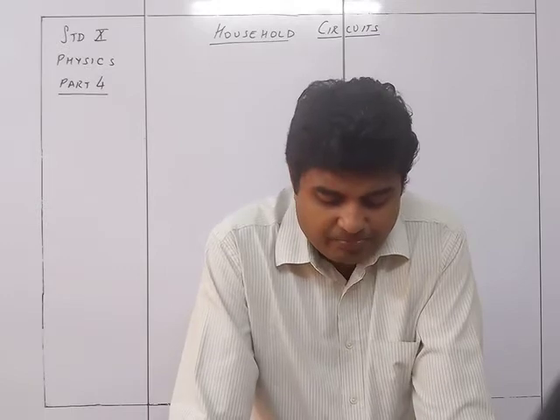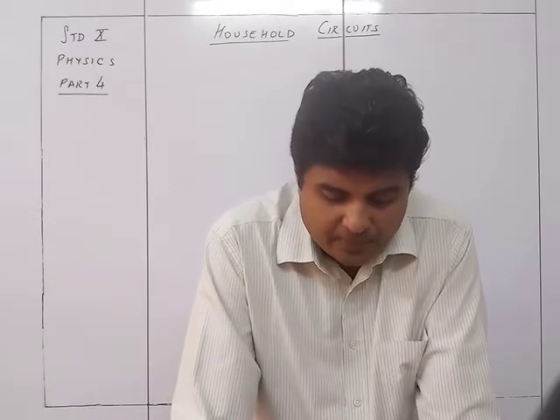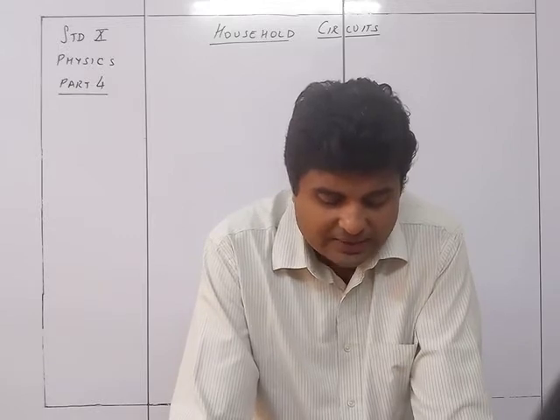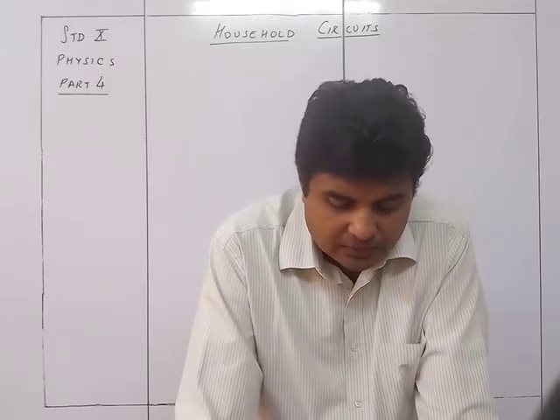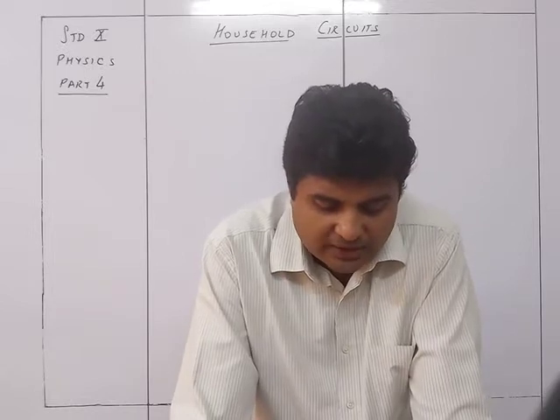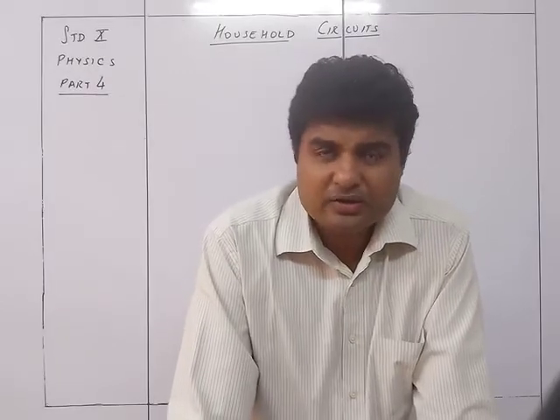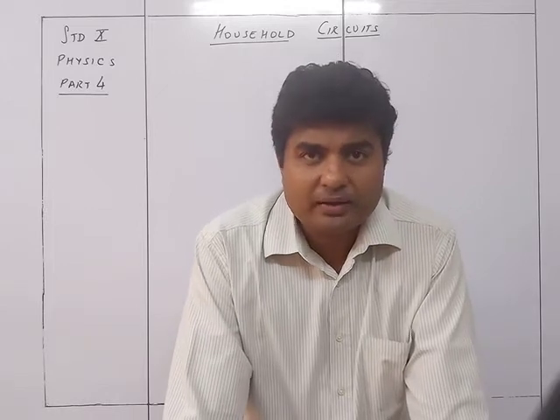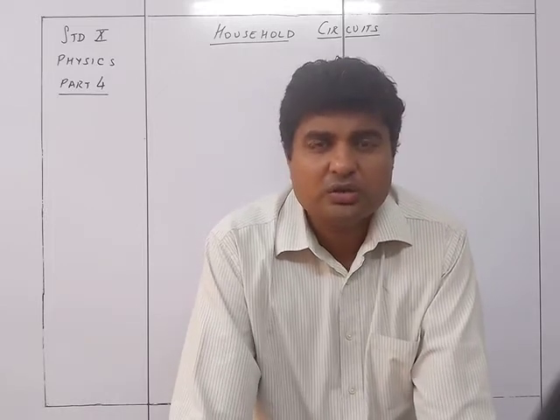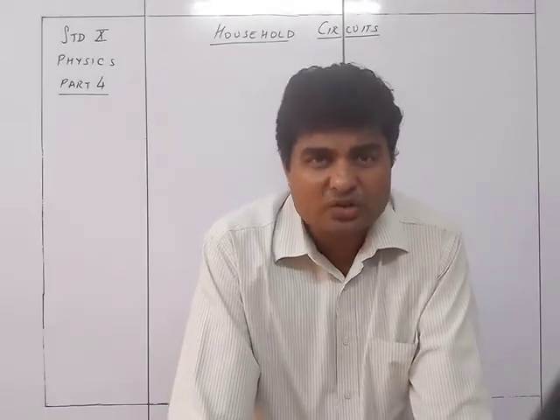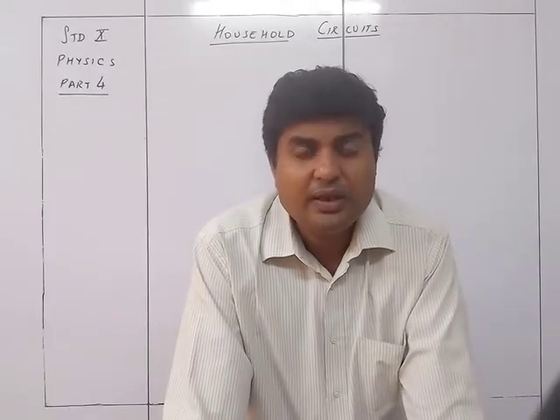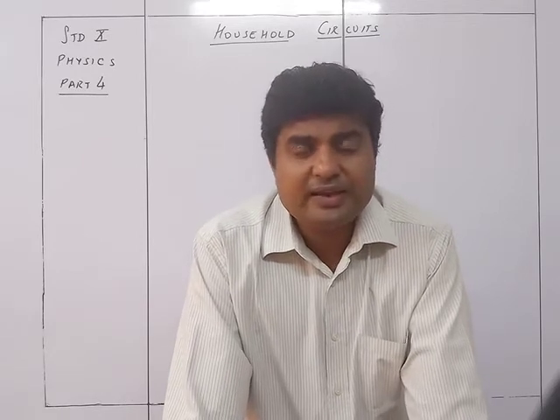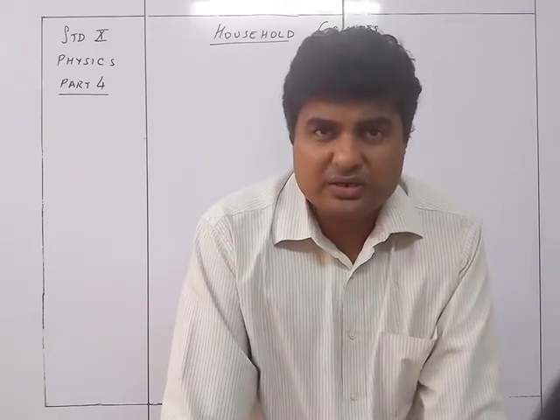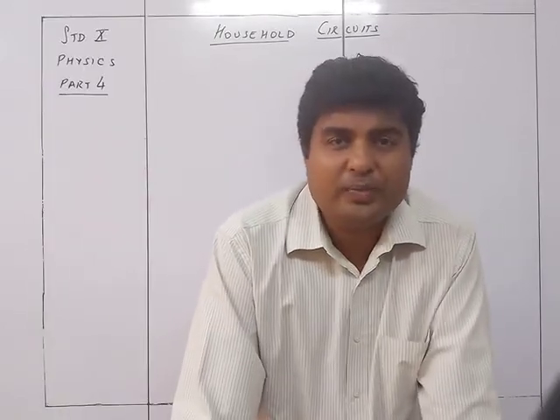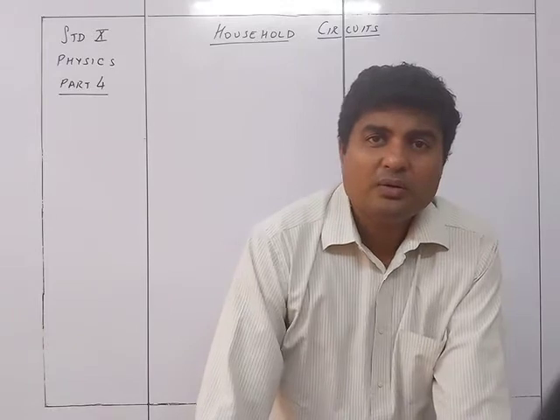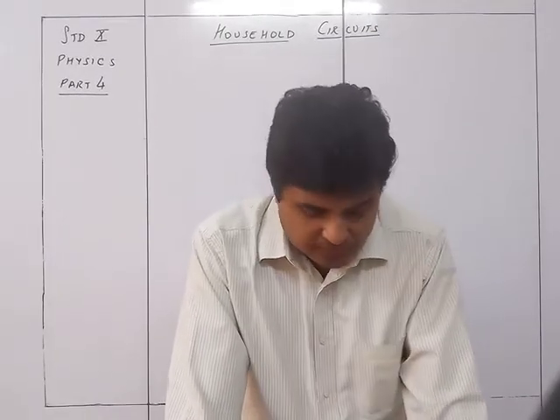To keep the ground damp, water is poured through the wire pipe from time to time. This forms a conducting layer between the plate and the ground. The upper end of the copper rod is joined with the earth connection at the kWh meter. So this is just an earth wire. So you are getting a firm connection with the earth for the complete circuit. In case of any fault, the leakage current, if there is any, is going to be drained out through the earth circuit. So that's why you need all this arrangement to be done just before the earth wire is connected to the kWh meter.